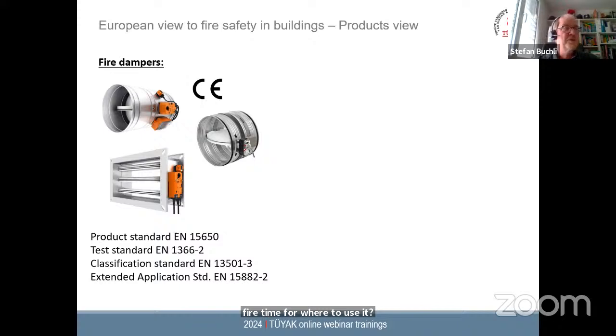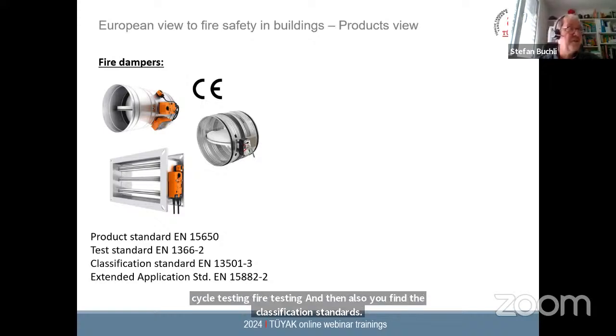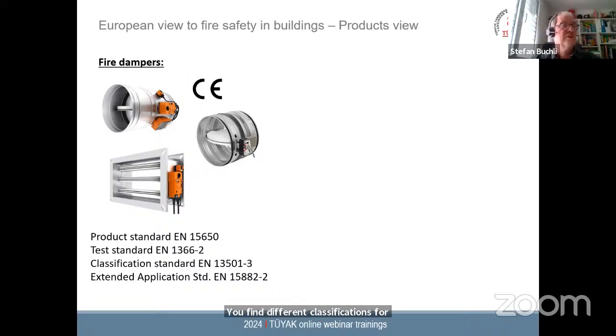And then it refers to the other standards where you find the test standard. How is this unit tested? This means mainly cycle testing, fire testing. And then you also find the classification standards. You find different classifications for these dampers. I will come to that point to give you an example. And then there is the so-called extended application standard. This is quite a new one for the fire dampers.